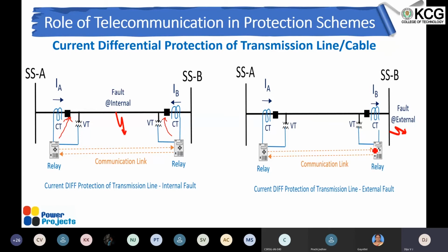It tries to calculate the sum of the currents in order to ensure that the fault is within the zone of protection. If there is a resultant current, or some current gives a value, then it issues a trip to the respective breakers. If it is external, then it is not going to trip.